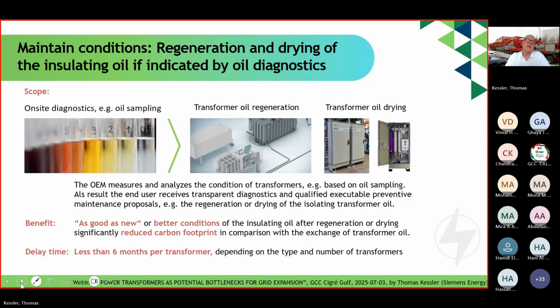So, starting, what can we do? I told you at the beginning, having a look at the stretch of the bathtub curve. First, what can we do to maintain the transformer conditions? The aging mainly takes place in the tank, which is why regeneration and drying of the insulating oil is important if indicated by oil diagnostics.